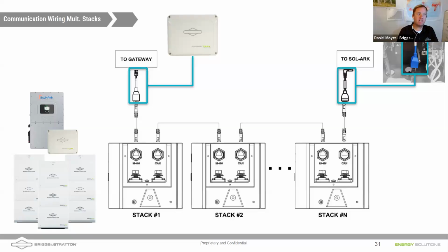Nathan, we have a question. Sure. What is the maximum number of 6.6 batteries that can be coupled or put together? We can put up to 18 of the modules together, right? So that's 6 stacks of 3. So we can do 6 stacks. That's 120 kilowatt hours. Now, keep in mind that you may be limited by other codes and regulations. If you're in a garage, for instance, you may be limited to 4 stacks or 80 kilowatt hours. So good question. Thank you for asking.